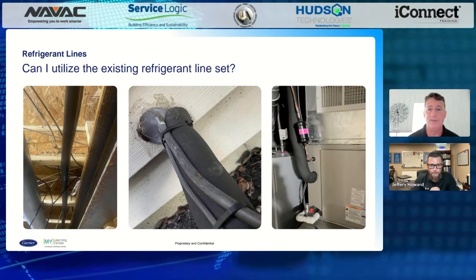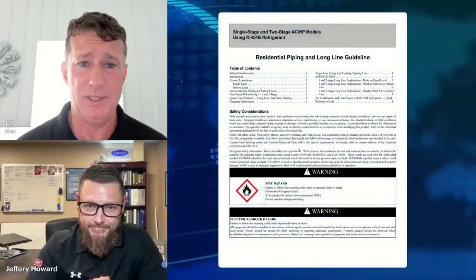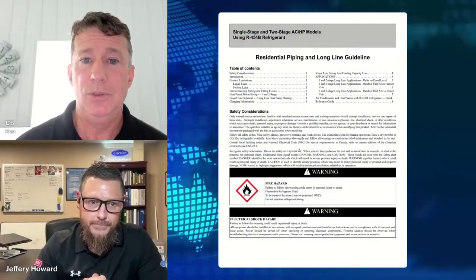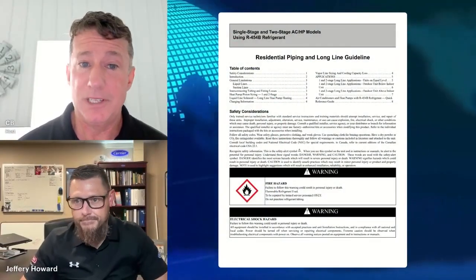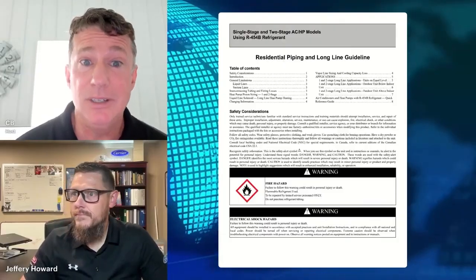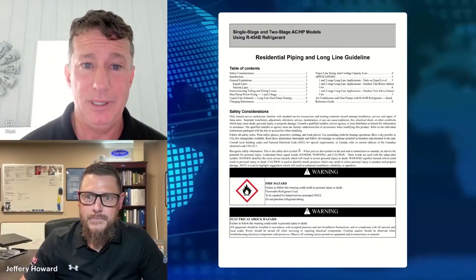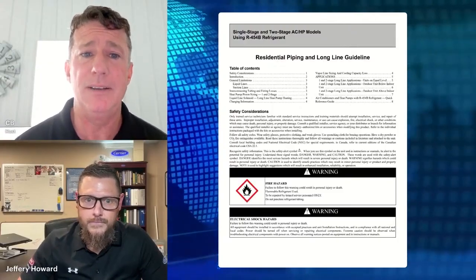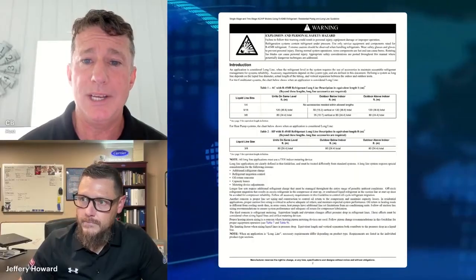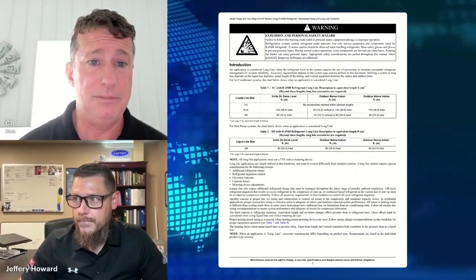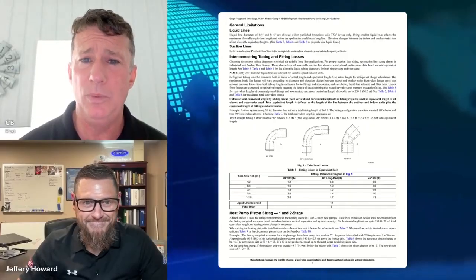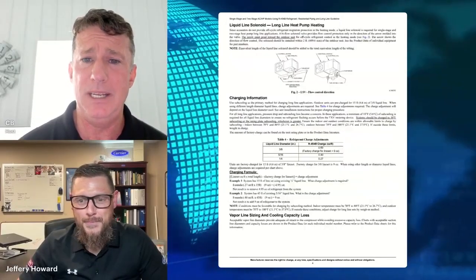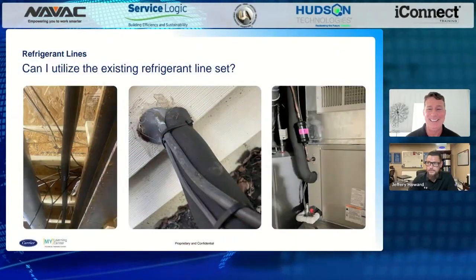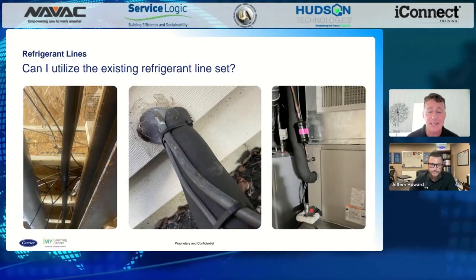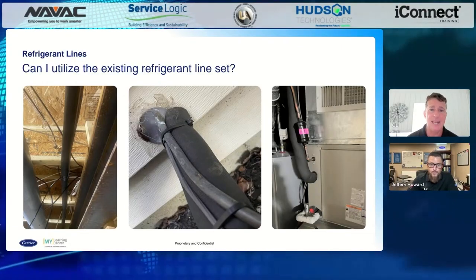A good reference point for everyone, if you're looking for information like where this comes from, go right into things like the long line set installation specifications. You can look in the standard installation manual for your outdoor unit and your matched coil, and you'll find a lot of the same specifications. You'll actually be able to determine if your line set is allowable for that size. I'll put some links here so you can come back to this PDF. I use it whenever I get questions like these. That's usually where I begin with my long line set installation instructions, because it has a lot of this information all in one place. Fantastic resource.